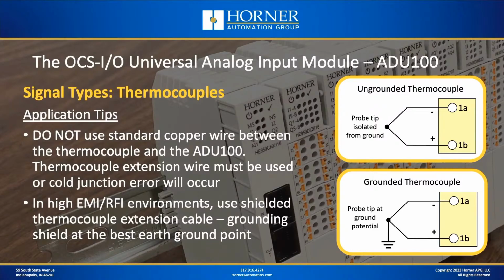Why is that important? Not every measuring instrument can handle both types of sensors. The ADU100 can handle both ungrounded and grounded thermocouples, but there are other products from other manufacturers, and even some products from Horner, that don't support both. For instance, the Smart Rail thermocouple module only supports ungrounded. The Model 6 I/O option for the XL series and the XL Prime only supports ungrounded, whereas the Model 5 XL series I/O option and XL Prime I/O option support both, and Smart Block thermocouple supports both as well.